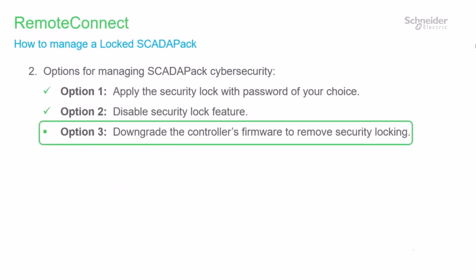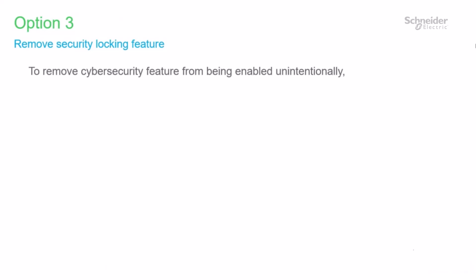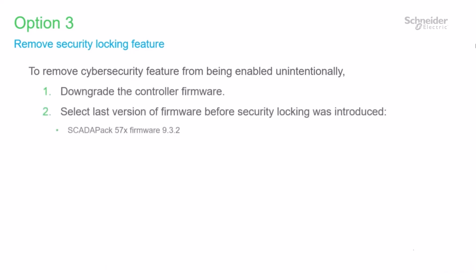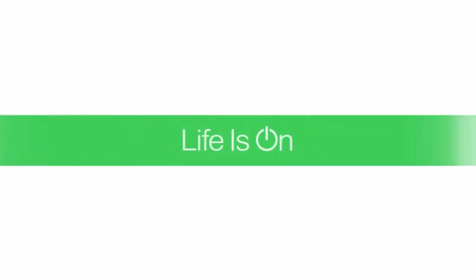Looking at the last option, to downgrade the controller's firmware and remove security locking: to remove the cybersecurity feature from being enabled on the SCADAPack in the future, we replace the controller's firmware with the last version before security locking was introduced for your controller type. This option may be helpful in the short term, but downgrading firmware means you are choosing not to take advantage of any improvements, fixes, or new features associated with maintaining up-to-date firmware.